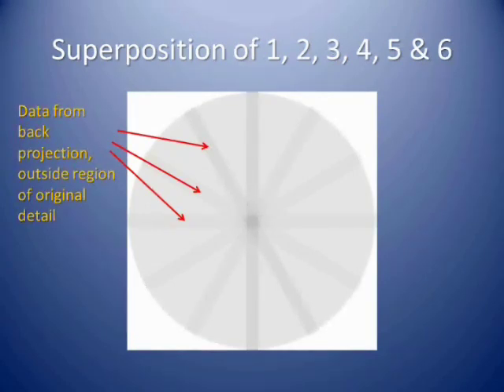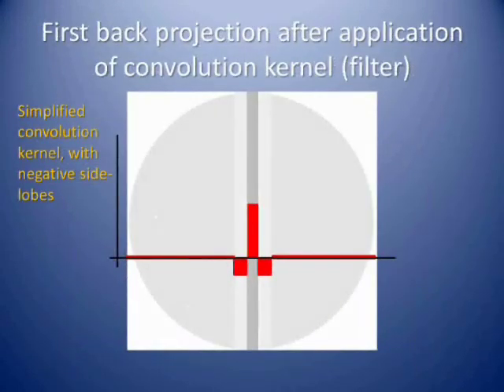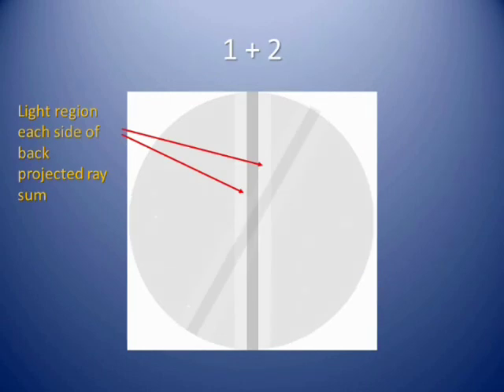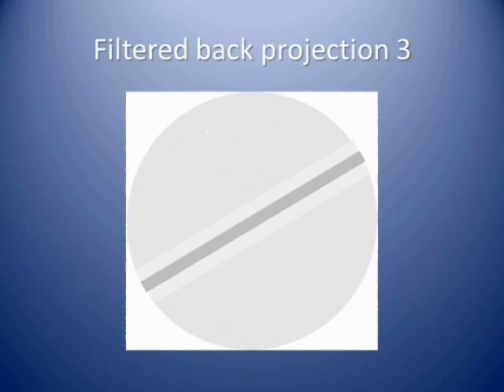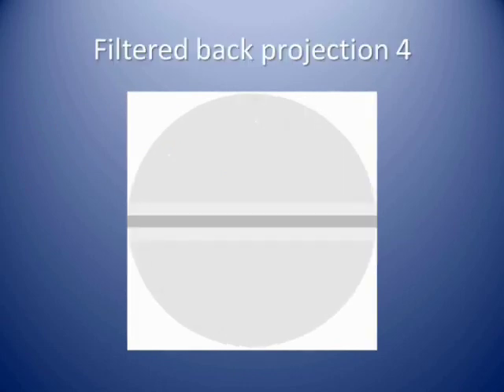To undo this blurring effect, we must apply a deconvolution. The deconvolution is based on a kernel shape, which is applied to each projection prior to their superimposition. As you can see, several of these back projected rays have been treated using the convolution kernel, which results in a light region each side of the main back projection ray.